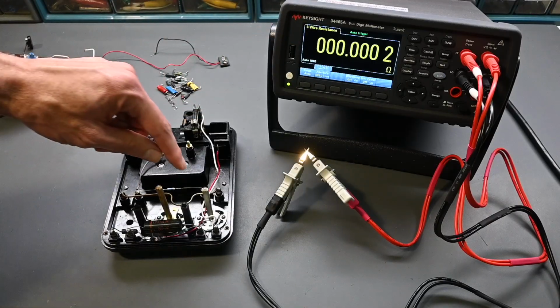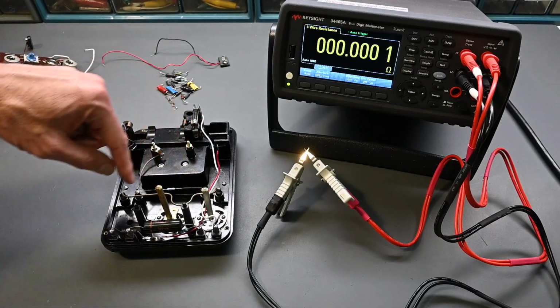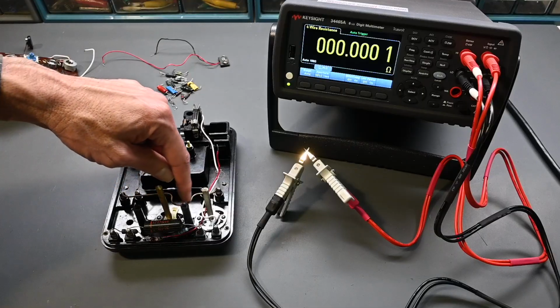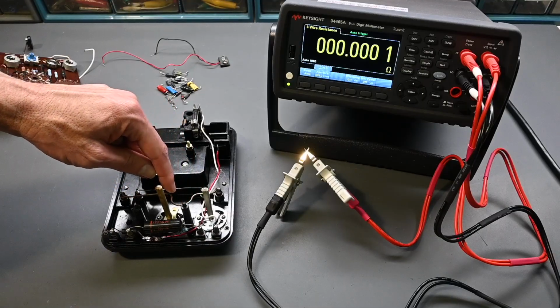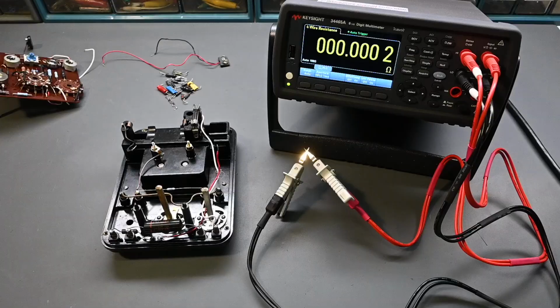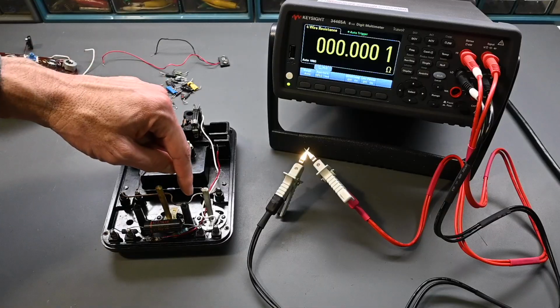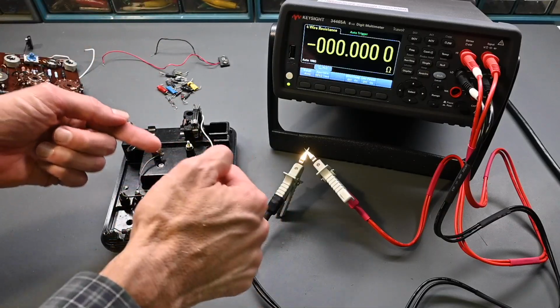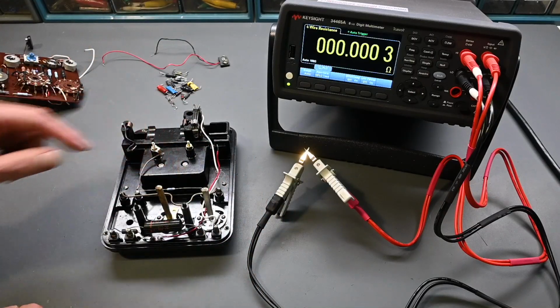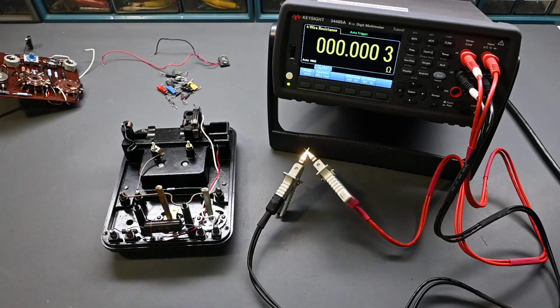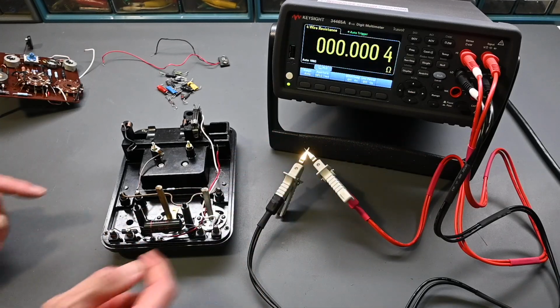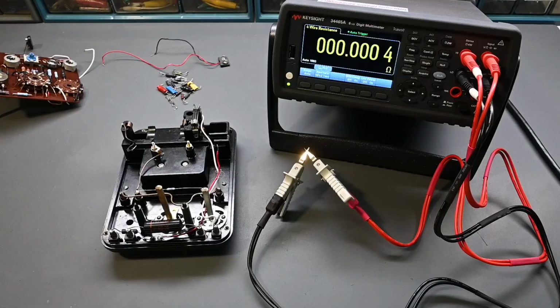So let's take a look at the 10 amp current shunt, which is this stiff piece of wire that goes through here. It has a very specific resistance. It's supposed to be 0.025 ohms, okay, very low value. And a traditional ohm meter isn't going to be able to measure this. It's going to look basically just like a short touching together, but there is a very specific resistance on that wire. So with the 4-wire mode like this, it makes measuring a shunt resistance like this very, very easy.